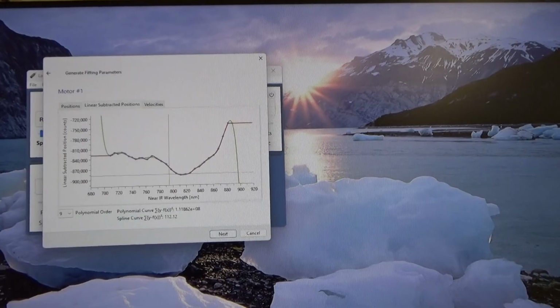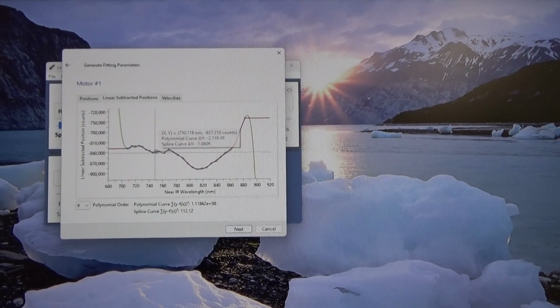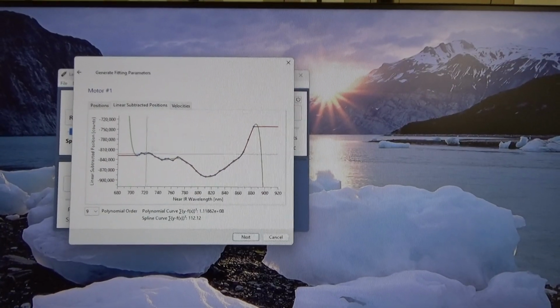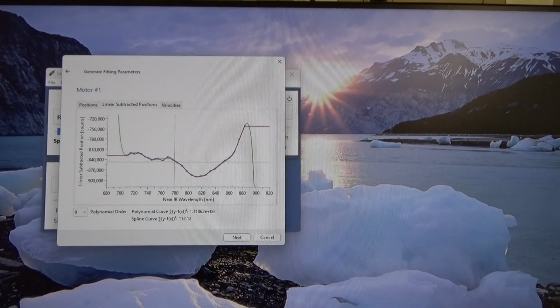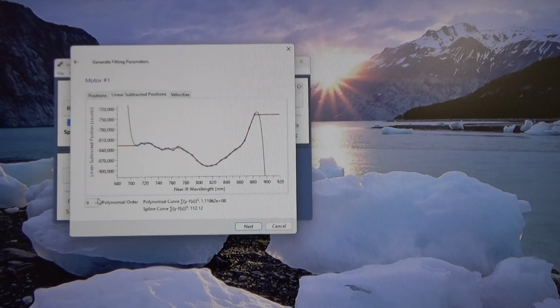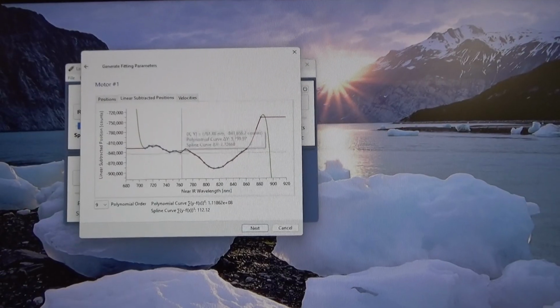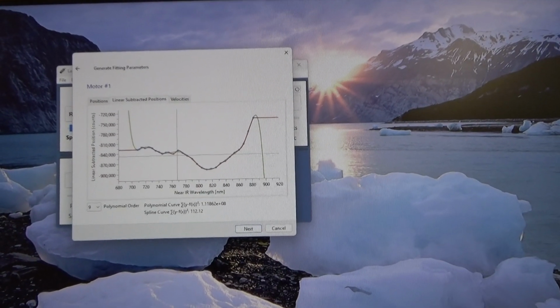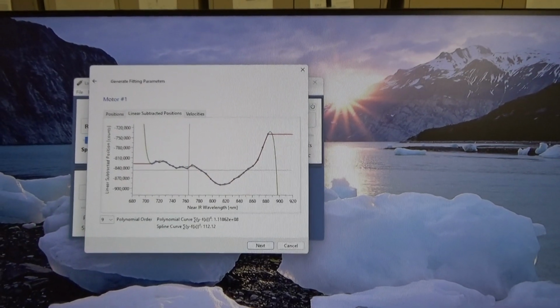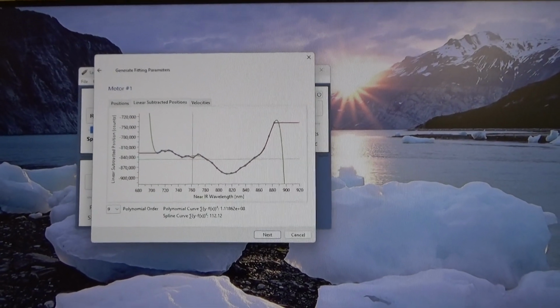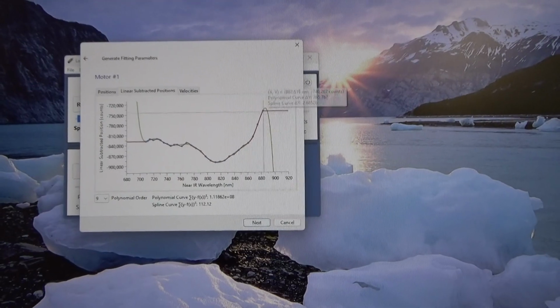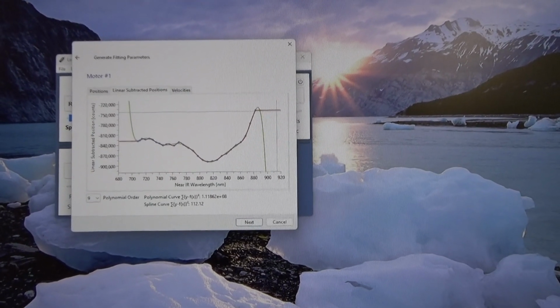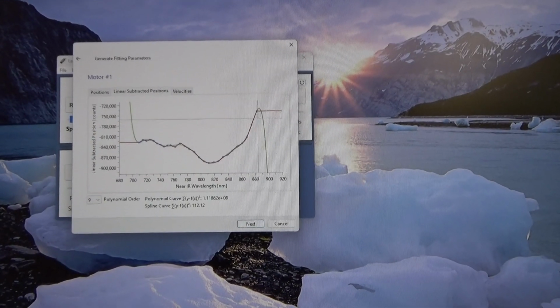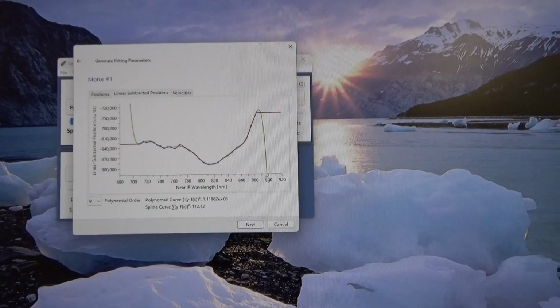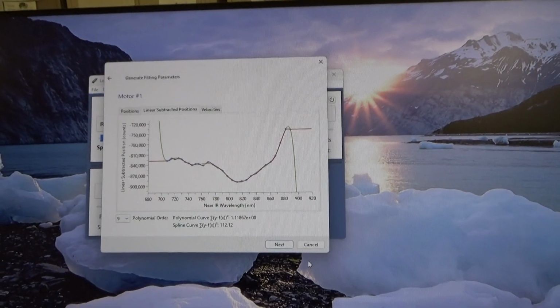The spline fit is actually quite nice because it can follow the actual behavior of the motor positions that you measured. And so any slight deviations that aren't taken care of by a ninth order polynomial can be fit by the cubic spline function. Now you can choose which curve you're going to be using in the setup window for each one of the motors. The really nice feature for using the spline fit is that the motor stops tuning if you go outside of the wavelength range. If you're using a polynomial curve and you go outside of the tuning range, the polynomial can just blow up and the motor will start spinning out of control.